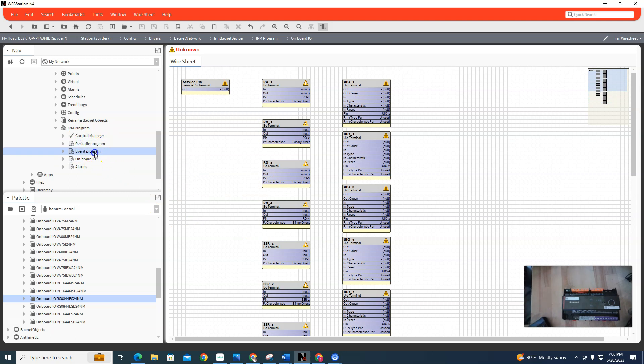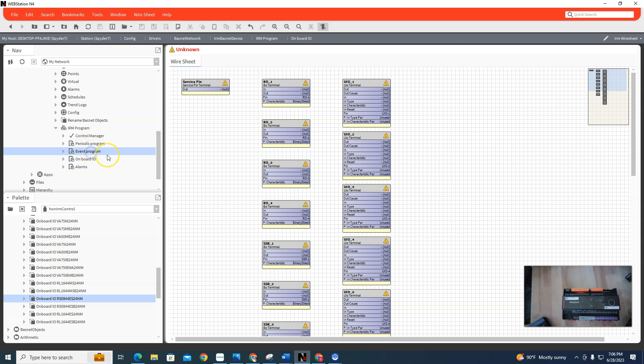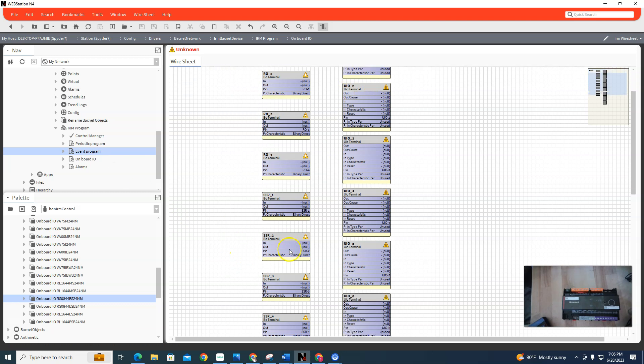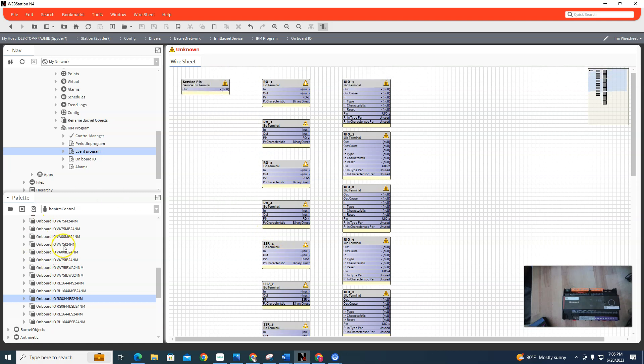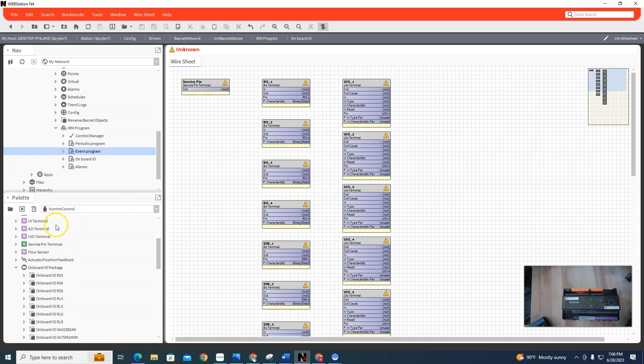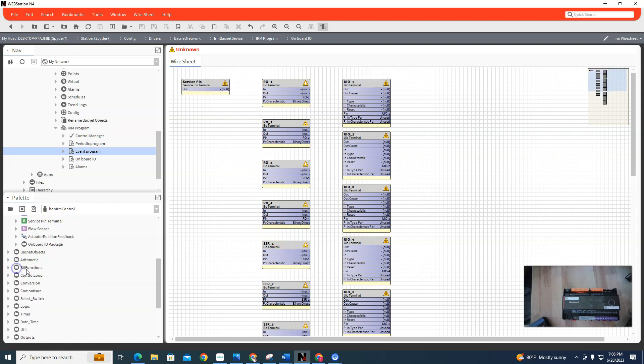Then you would put your programming either in periodic programming or event. Periodics are time-based - it runs the complete programs in milliseconds. Every so many milliseconds it looks at the programs and reruns it. Event programs run them immediately based on an event, so a status change - boom, it runs a program. If it doesn't have an event, I think it runs periodically. Don't get me lying, I'm not the Honeywell expert, I just know enough about them to be dangerous. Then you use this Honeywell IRM control palette to do all your programming in those two folders right there.